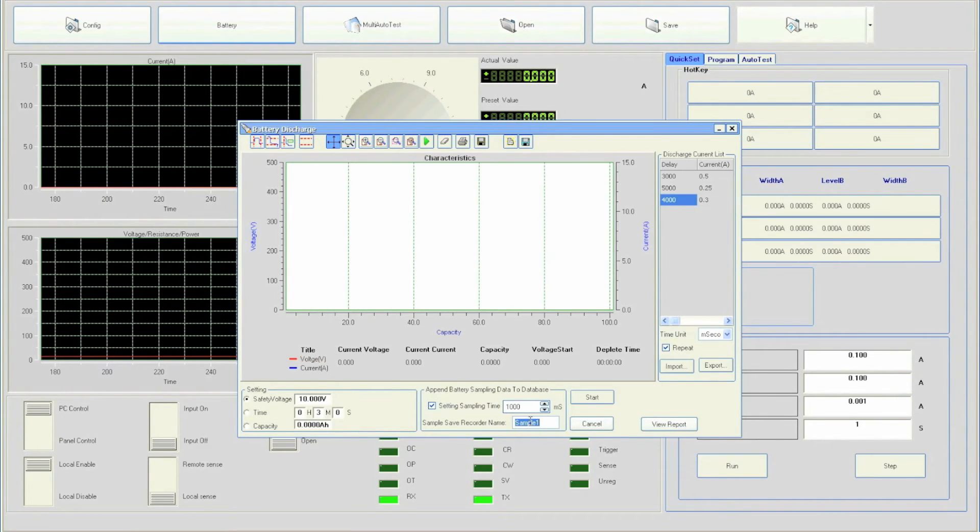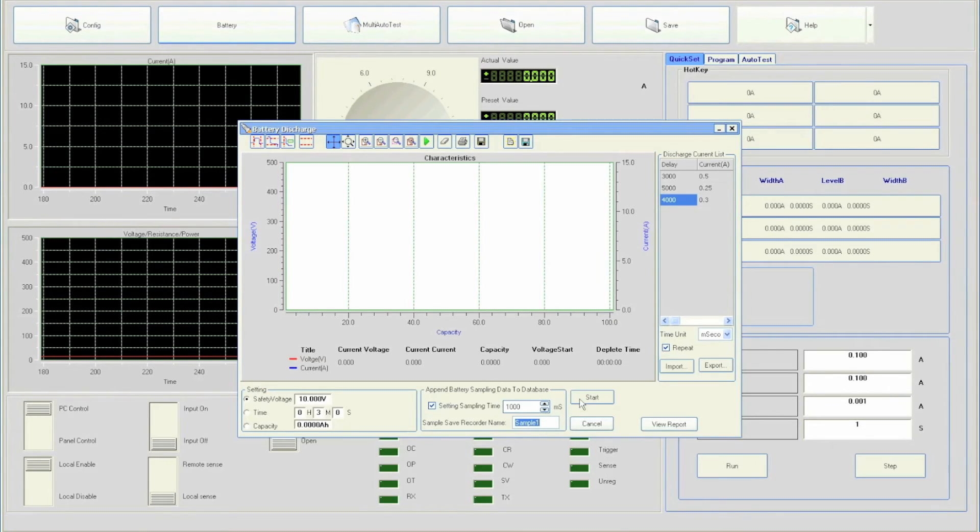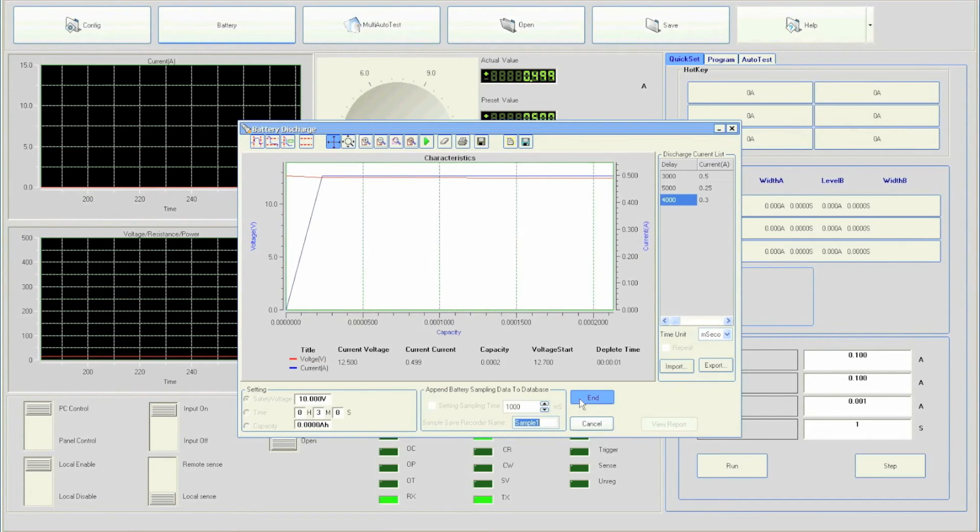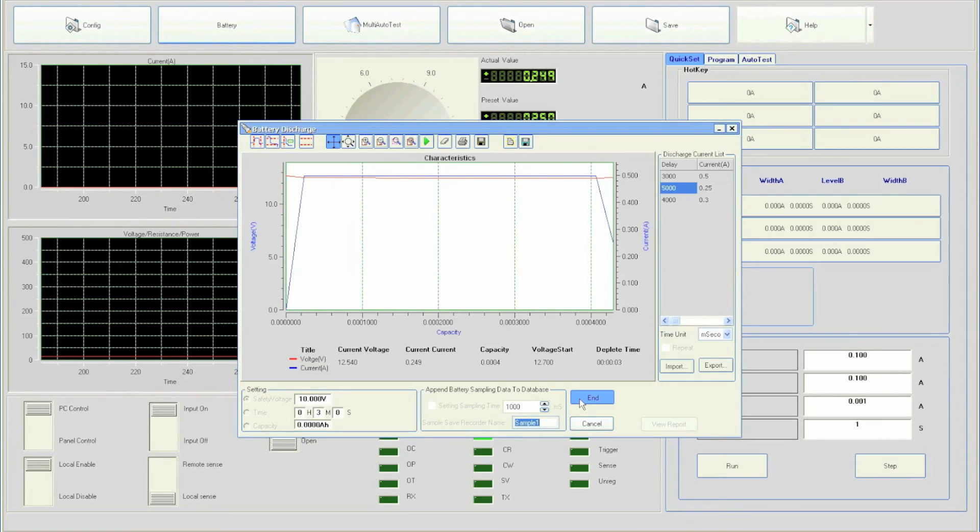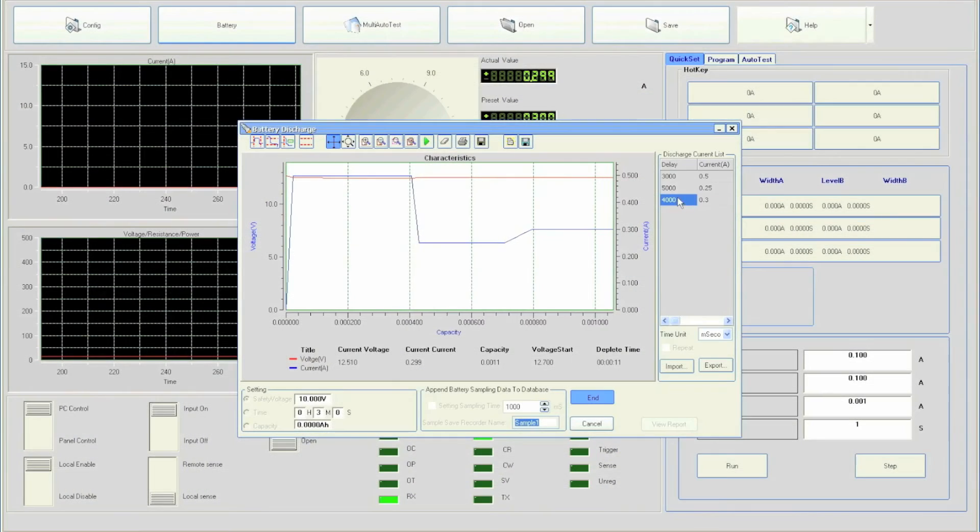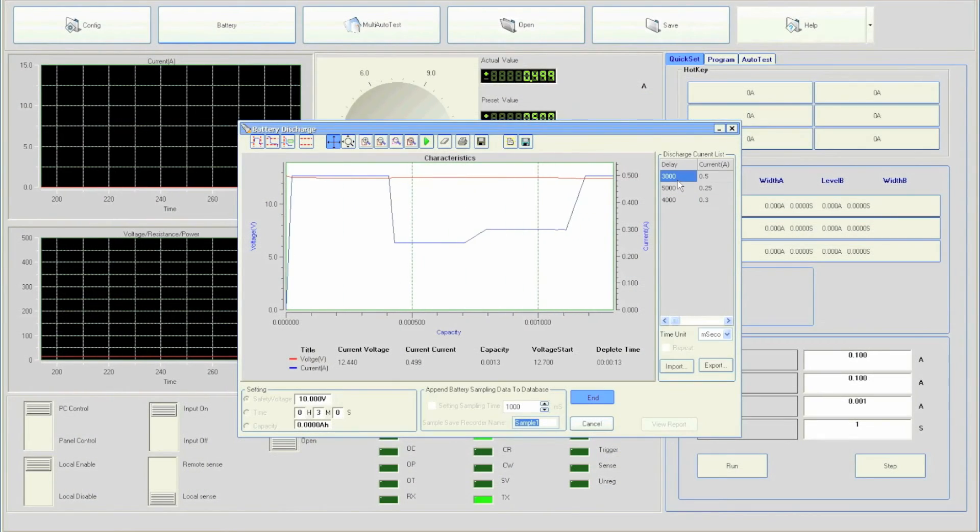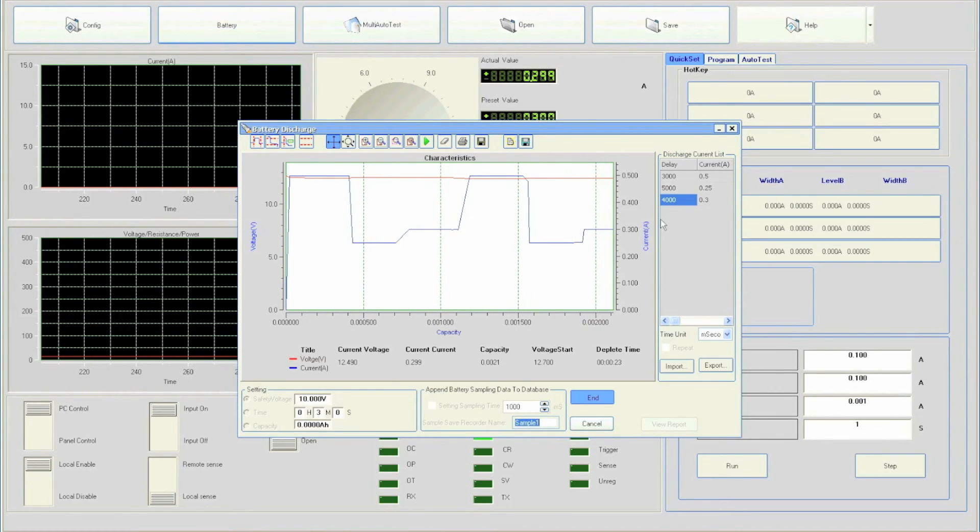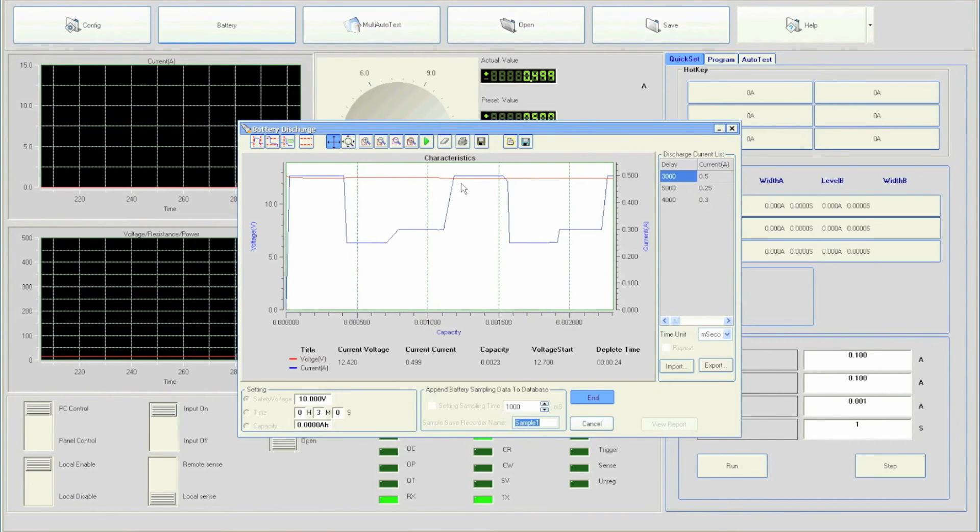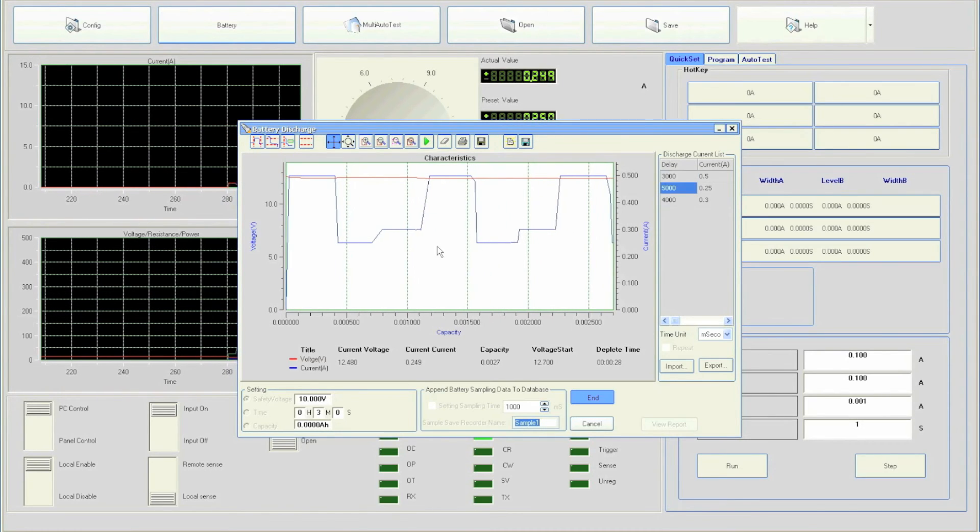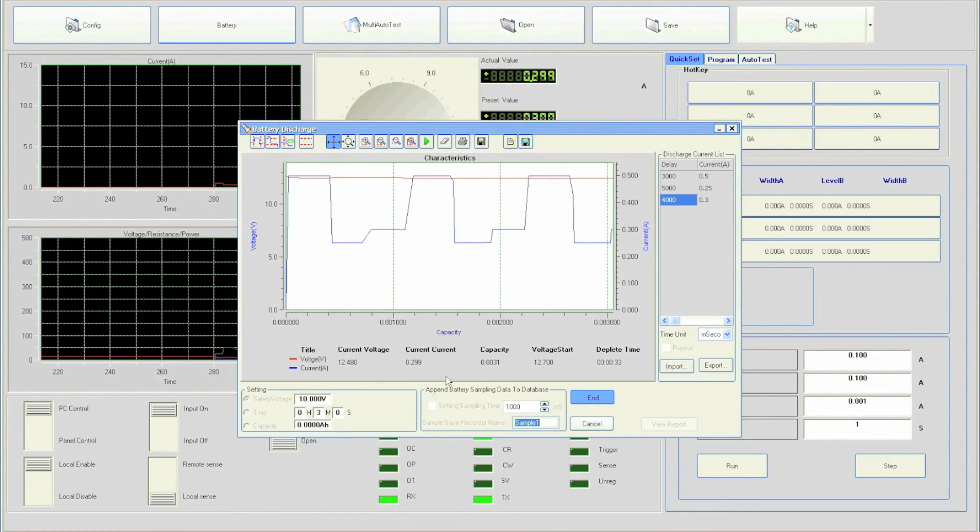Click the start button to begin testing. The load will start testing the battery using values set in the discharge current list. You can see the test going through each step by the highlighted box shown here. The graphical display will plot the voltage and current throughout the test. Voltage is in red and current in blue. Notice that capacity as well as depletion time will be monitored constantly until the test ends.